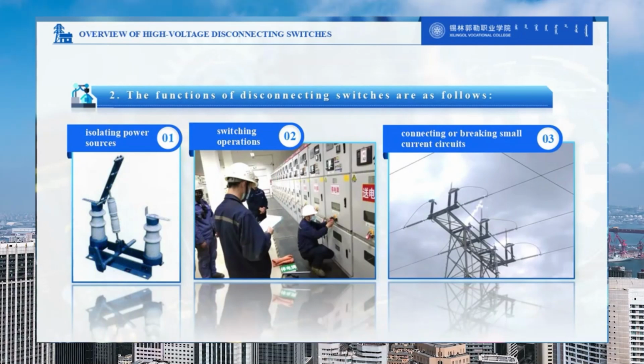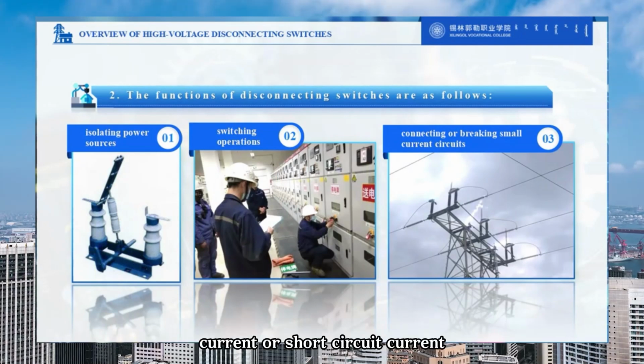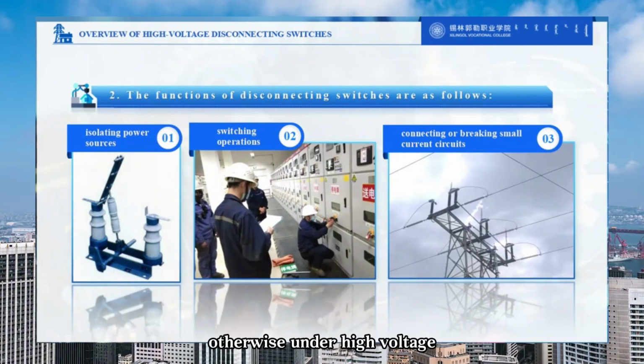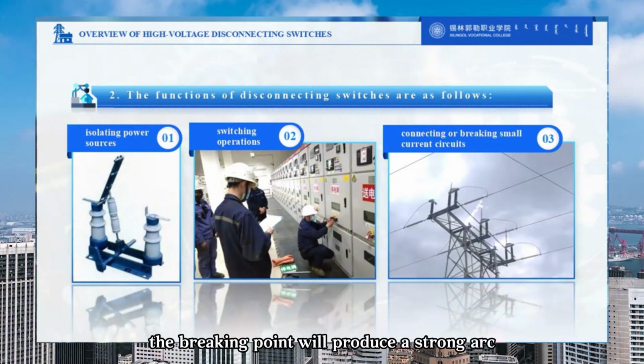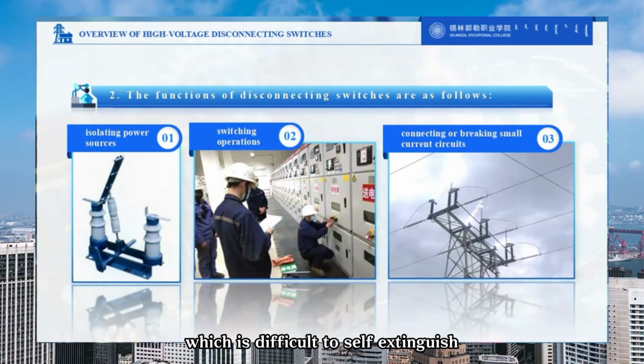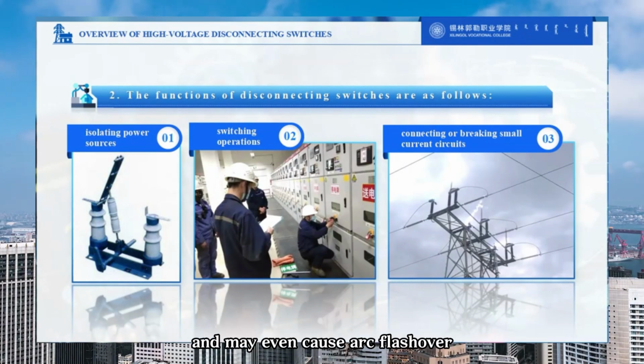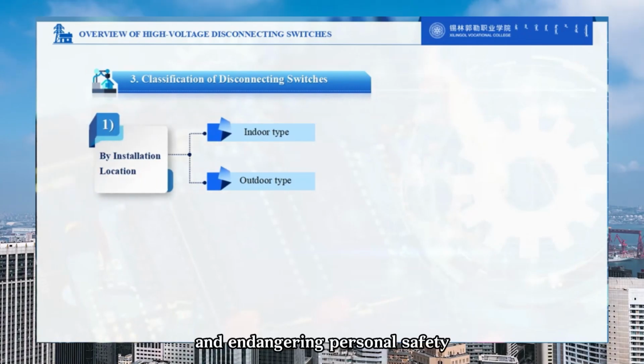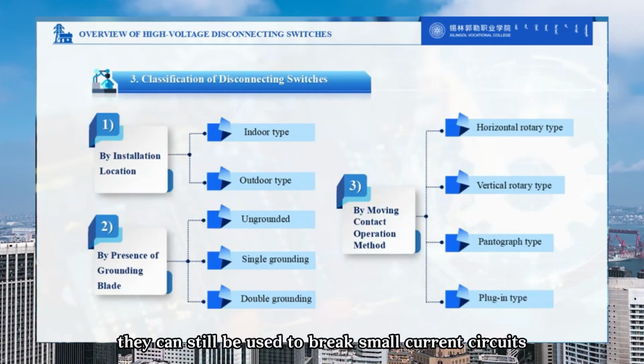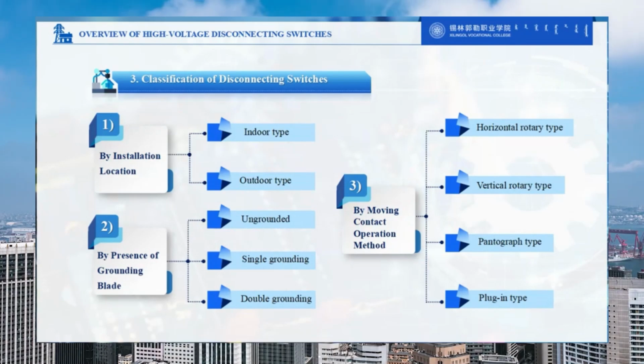Disconnectors have no arc extinguishing device. Therefore, they cannot be used to cut off load current or short-circuit current. Otherwise, under high voltage, the breaking point will produce a strong arc, which is difficult to self-extinguish and may even cause arc flashover, burning out equipment, and endangering personal safety. However, they can still be used to break small current circuits.